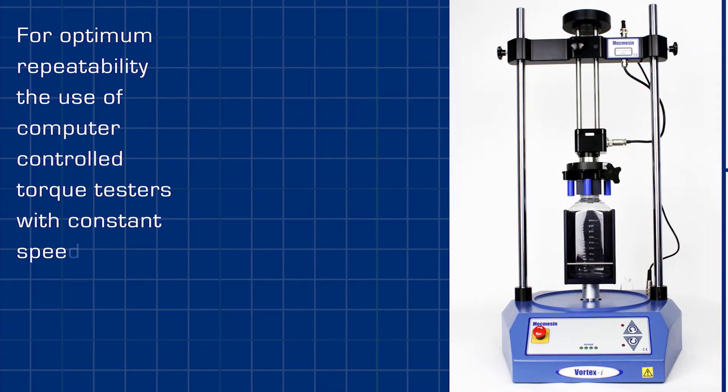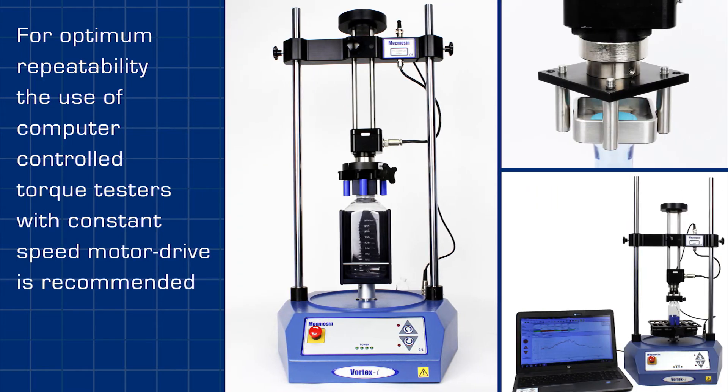For ultimate repeatability, constant control of test speed is required. This is achieved by using computer controlled torque testers such as Mecmesin's Vortex-i or XT.